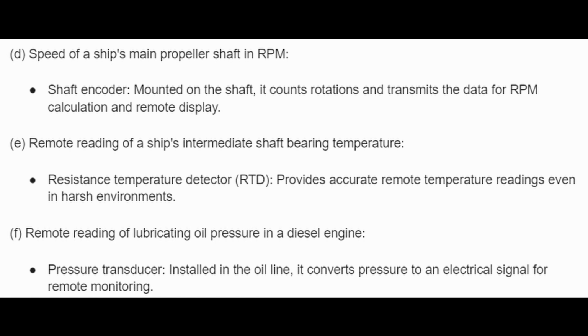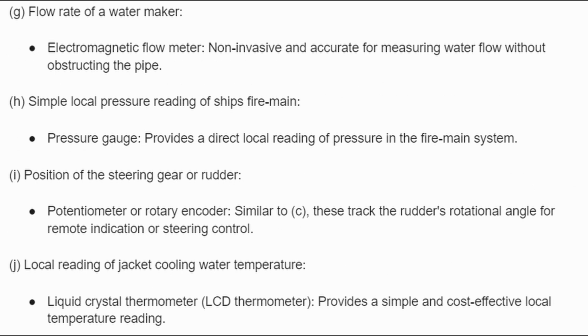F. Remote reading of lubricating oil pressure in a diesel engine. Pressure transducer installed in the oil line. It converts pressure into an electrical signal for remote monitoring. G. Flow rate of a water maker. Electromagnetic flow meter. Non-invasive and accurate for measuring water flow without obstructing the pipe.